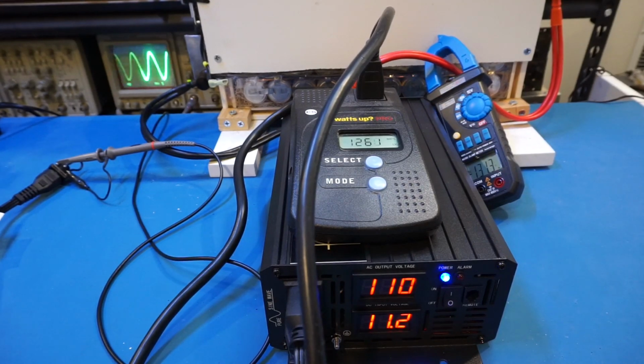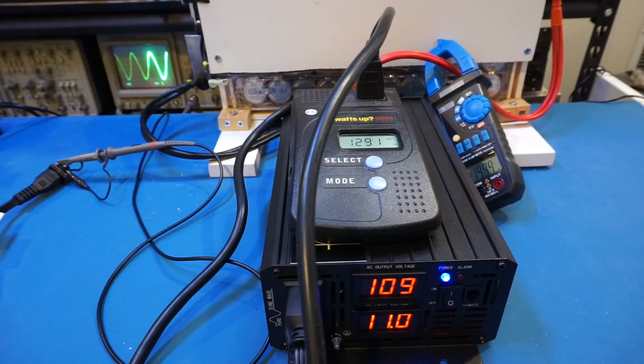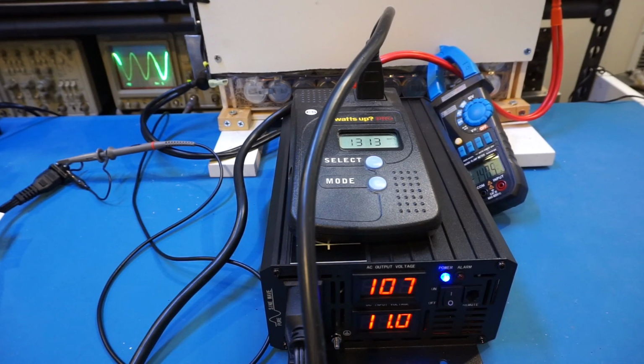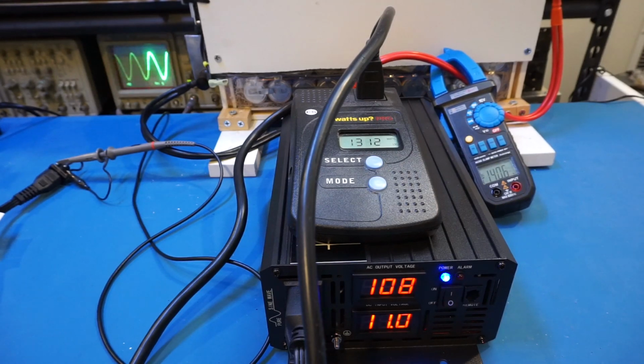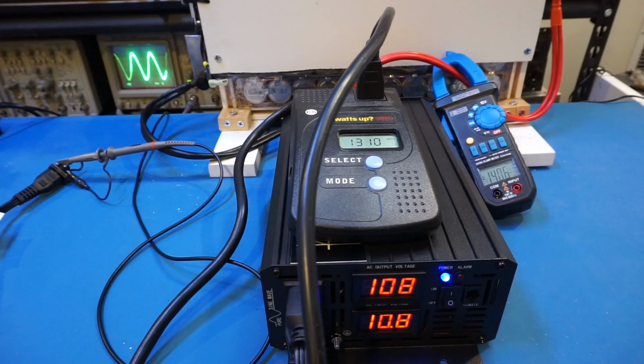Let's keep increasing and see at what point we trigger the load protection here. So wait a second, it's only at 1300 watts and you heard that alarm. I'm not sure if that's just warning you it's approaching the limit, or if it's actually exceeding it, but the limit should be at 1500 watts. Let's see at what point it shuts off. Let's keep increasing, so 1300 watts.